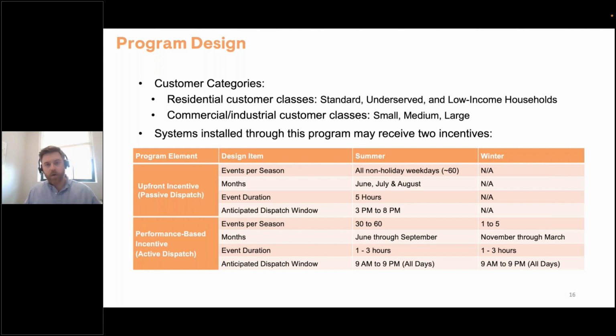Any time we call an active event for the performance incentive, it will overlap with these passive events, so we'll cancel the passive event for the day. We expect in late July, August, and a bit into September, on really hot peak days, to cancel a lot of passive events and do active ones instead—a 3-hour, up to 100% discharge instead of the 5-hour 80% discharge.